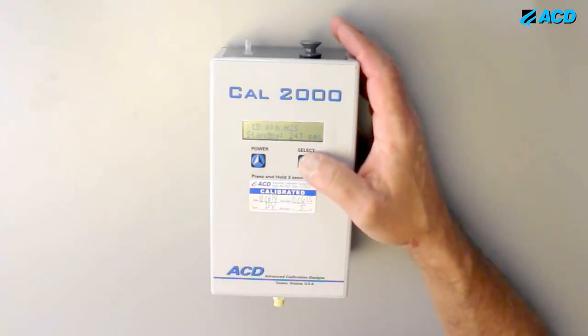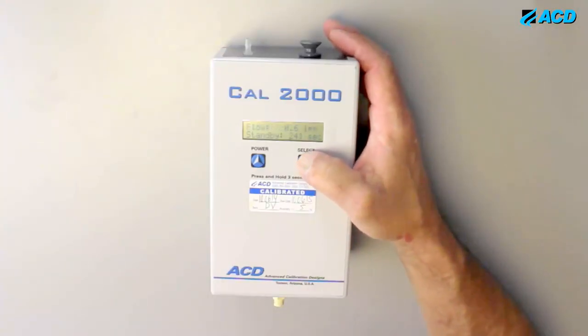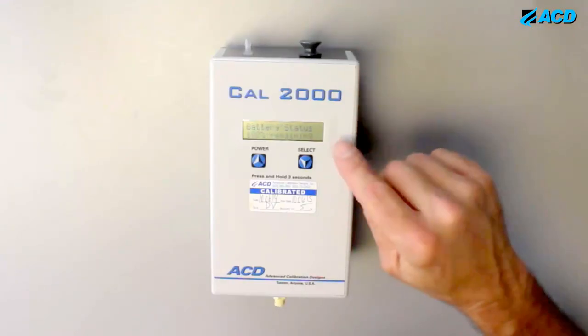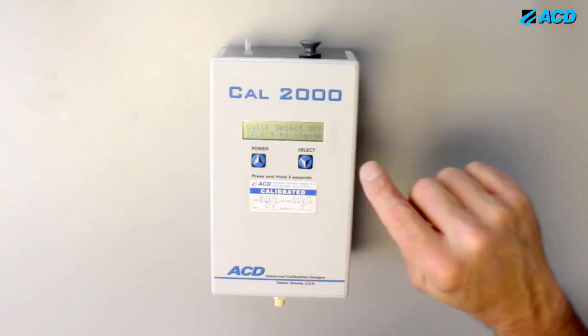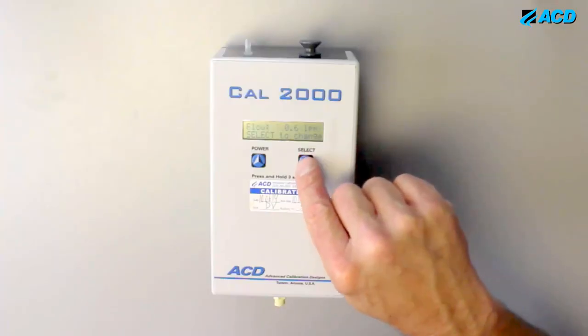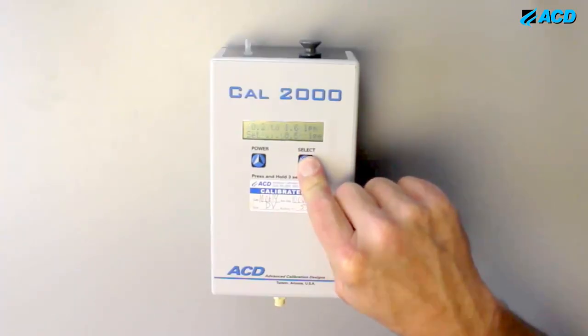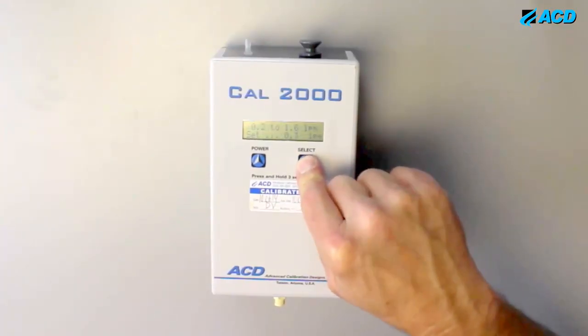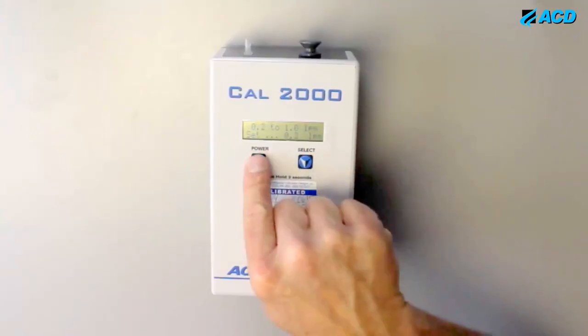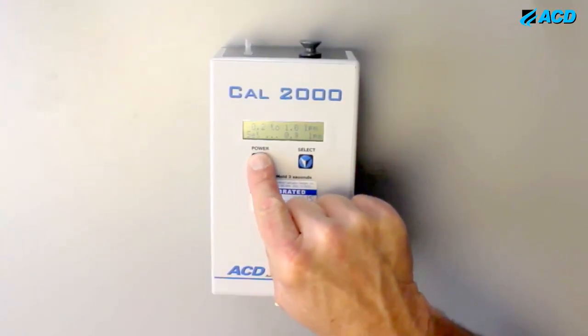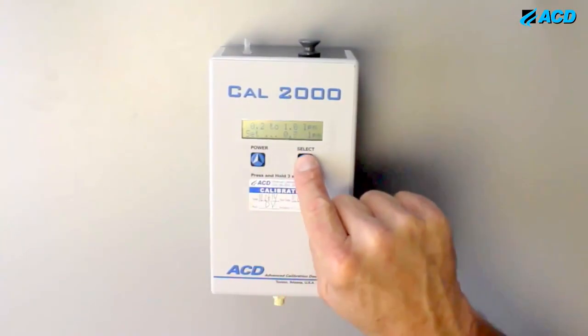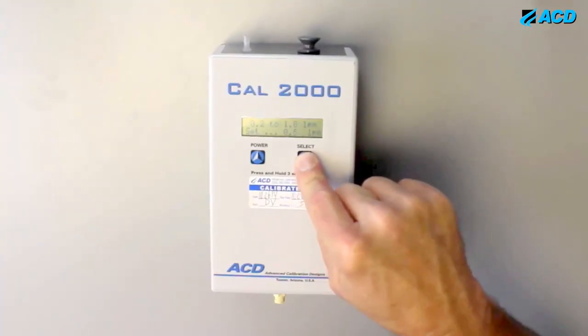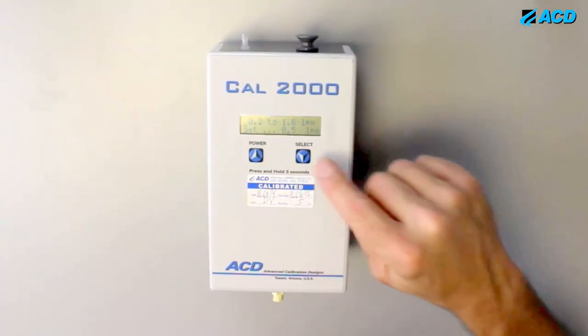So let's say now I don't want 15 parts per million or 0.6 liters per minute. I want to change that. So I hit the select. It shows me the battery status, this quick select function, and the 0.6 for the flow rate, and it says select to change. And now here's where the power and select become up and down arrows, okay? So I'm going to set it at popular flow rate, which is 0.5 liters per minute.